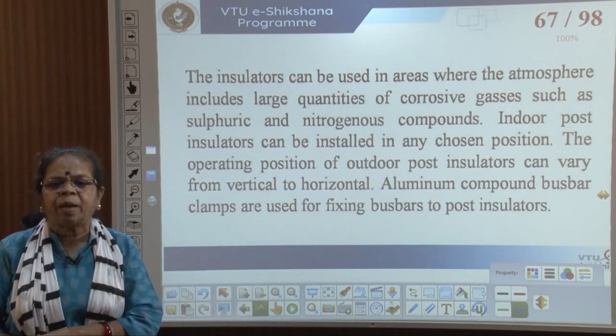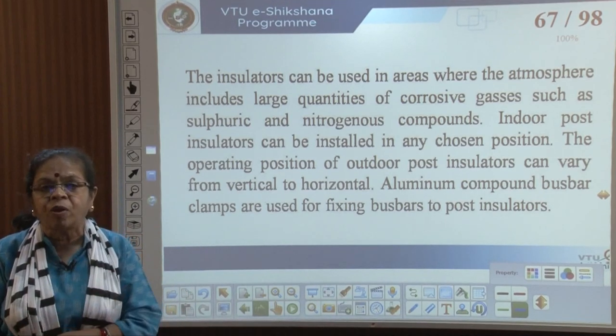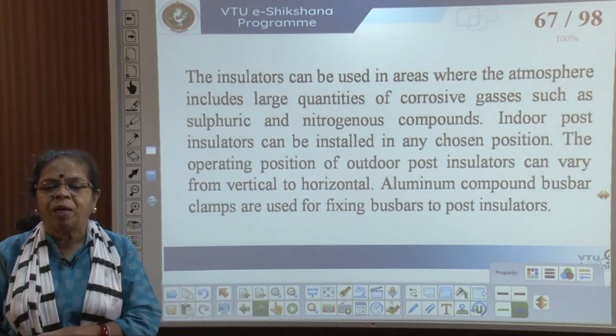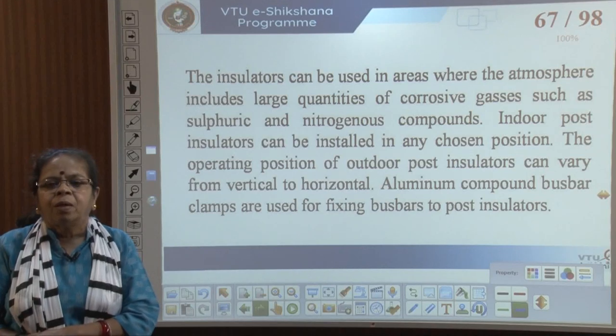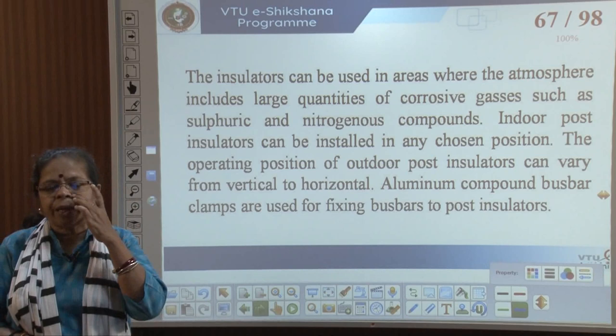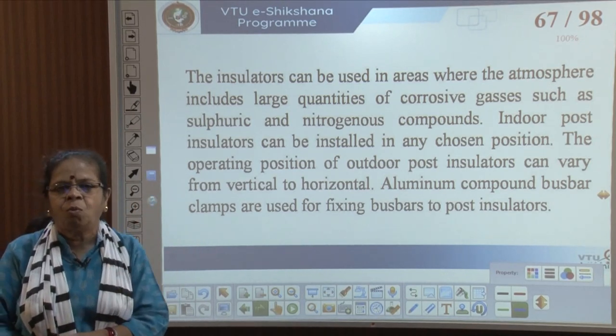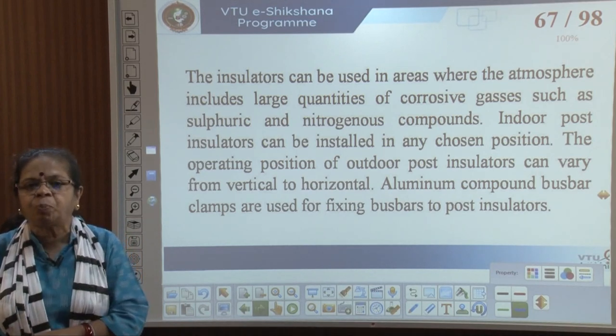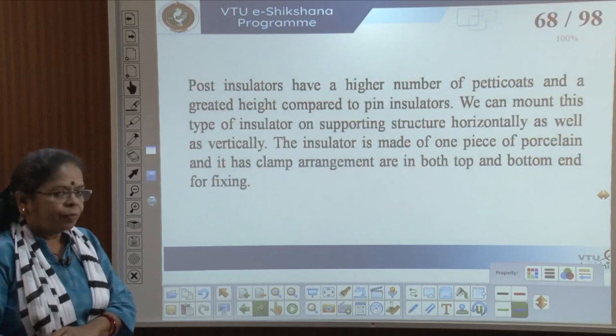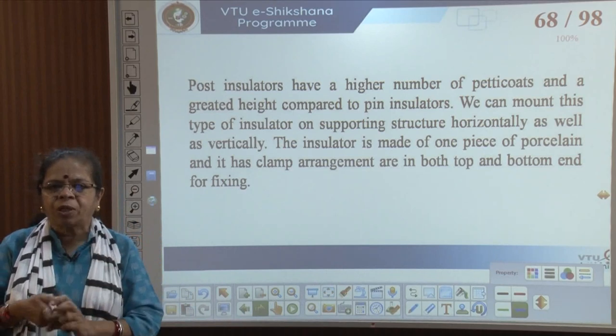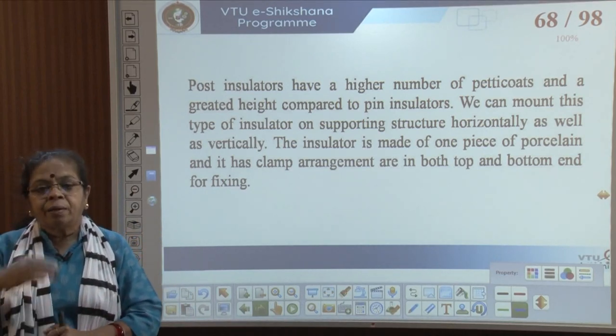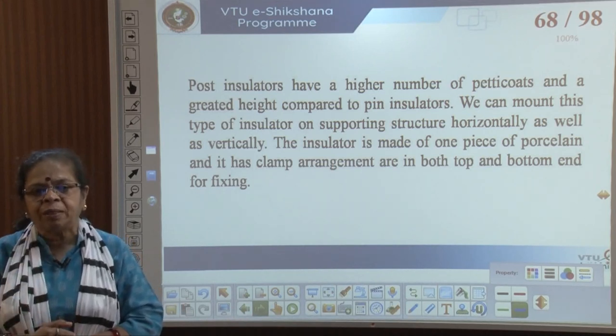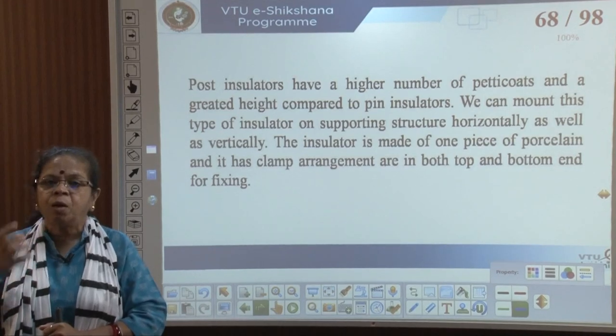Post insulators can be used in areas where the atmosphere includes large quantities of corrosive gases such as sulphuric and nitrogenous compounds. Indoor post insulators can be installed in any chosen position, and outdoor post insulators can be placed horizontally or vertically depending on available space. Aluminium clamps are normally used for fixing bus bars to the post insulators, and the insulator is typically made of one piece of porcelain with clamping arrangements at both top and bottom.